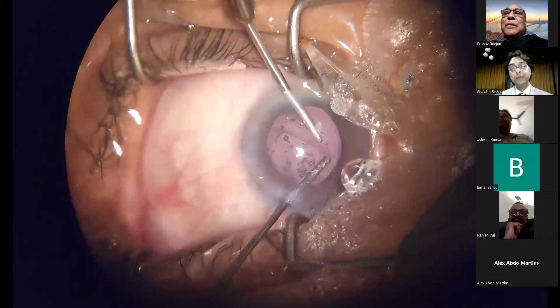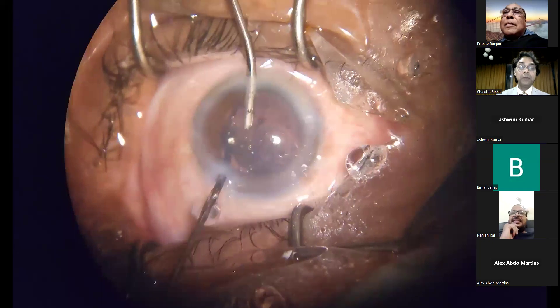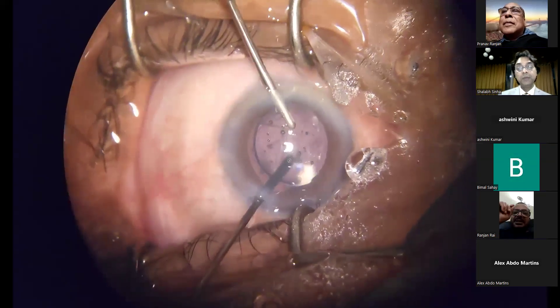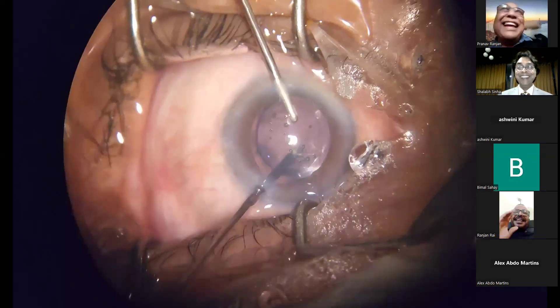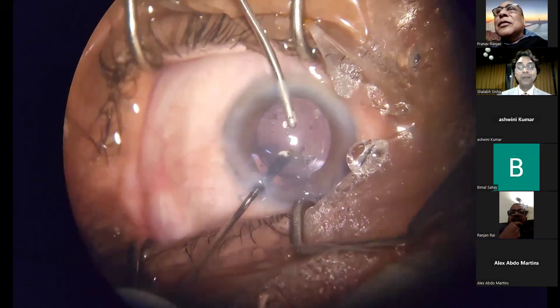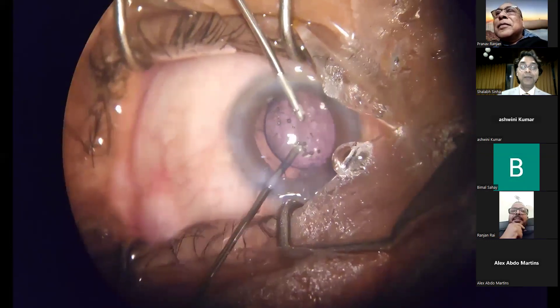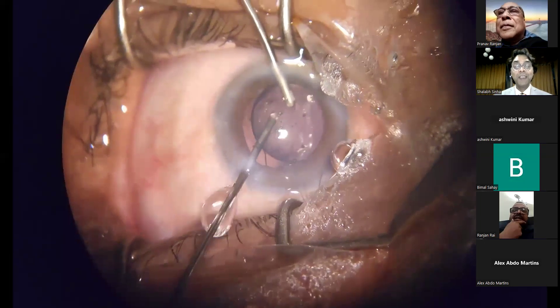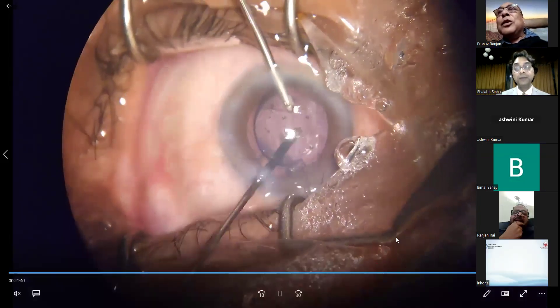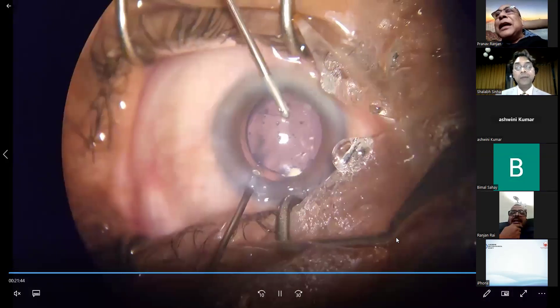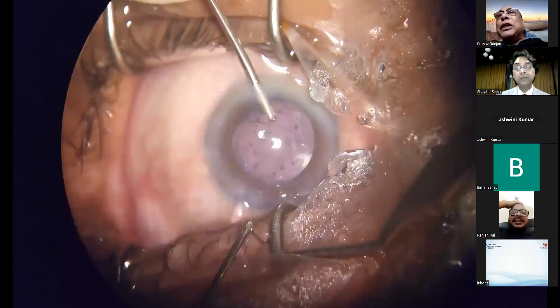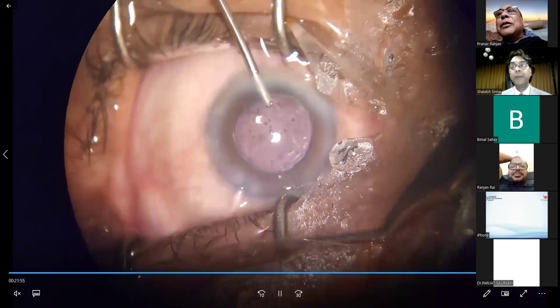Dr. Ranjan comments: I visited my OT register for the last five years and noticed that I had most of my PCR rents in the month of February only. I thought January was too hectic and February would be more relaxing — it could be some sort of burnout for the surgeon. The suggestion is: visit your machine and check the parameters, whether the machine is functioning well. I faced a similar crisis a few months back where the aspiration was not functioning as per the required settings, and once it was sorted out, things eased out.